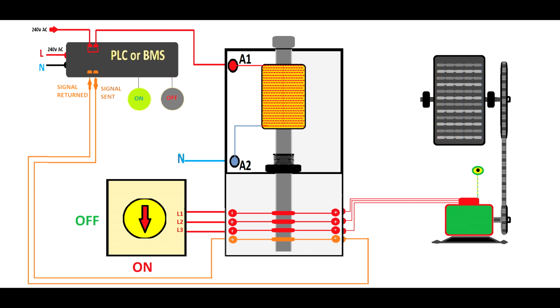As you will see now, when you enable the contactor, the motor starts turning, and you will see there's an input which goes from the PLC into the contactor and then is returning. That tells the engineer who is monitoring this system via the internet that the contactor is enabled. But most of the time the integration is wrong, because onto this HMI you can read that the motor is healthy, and that's very bad.